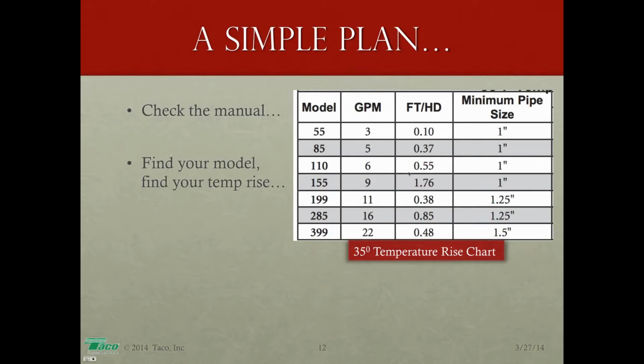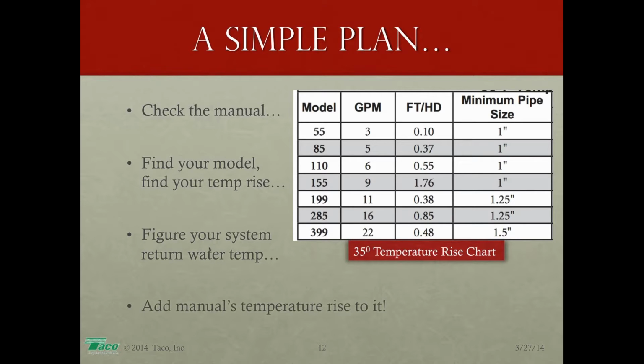So here we know the flow rate is 5 gallons a minute across the boiler. We know the minimum pipe size is 1 inch. Okay? So we find that information. Then we figure out what our return water temperature from the system is going to be under design conditions at that 20 degree delta T. In this case, we're going out at 140. We're coming back at 120. Well, then just add them up. Add the manual's temperature rise, 35 degrees, to the 120, and we get, ta-da, 155 degrees. That's a little bit easier than doing all the math, but at least you know where those numbers come from and what happens at the boiler.